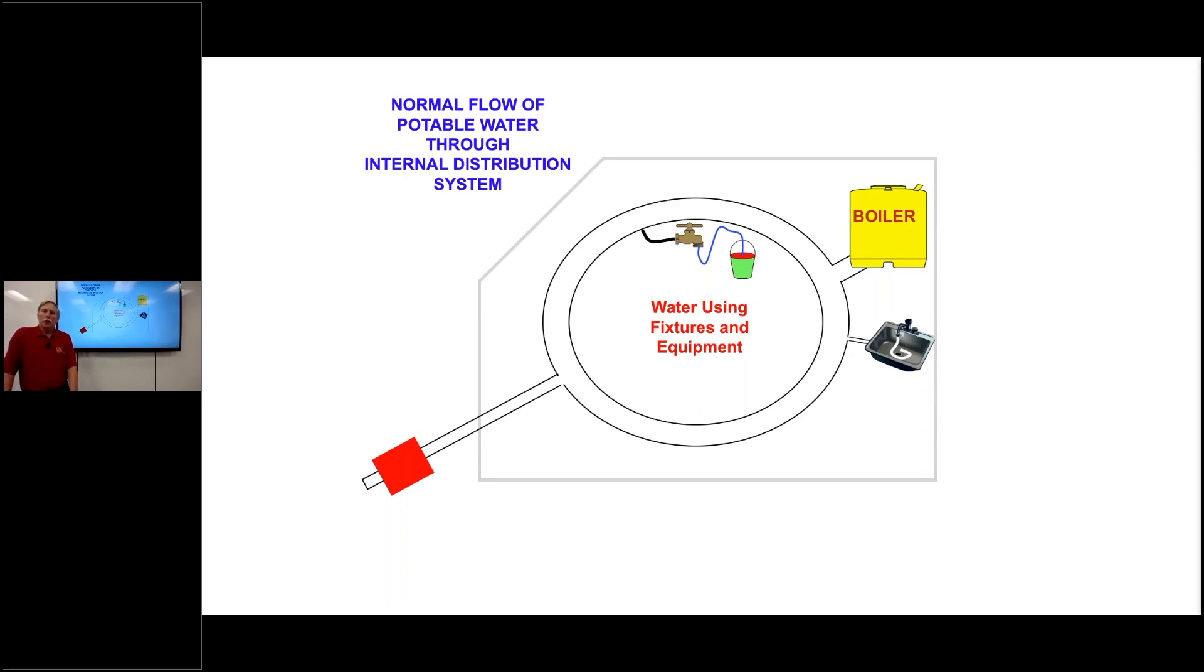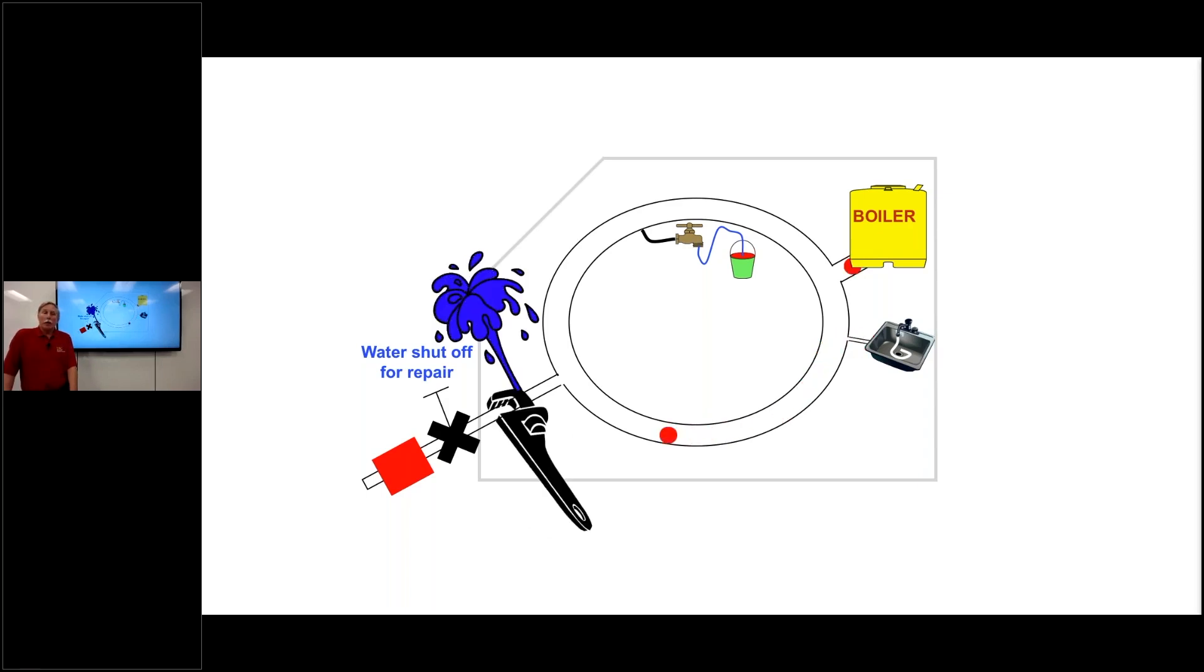So if we look at that same internal plumbing system now, and let's say as the water flows in, it goes to all its respective uses within a building, within a residence too. Should there be some need for repair on that internal plumbing system and the water system is shut off, we've now suspended the water in the distribution system within the building. And then once that repair is made and maybe there may be a depressurization, you see that without proper backflow protection at each of the water using fixtures or water using equipment, there could be a backflow within the internal plumbing system. Keep in mind the backflow preventer out at the service connection prevents it from getting back into the distribution system. However, the contamination within the facility could be taking place.